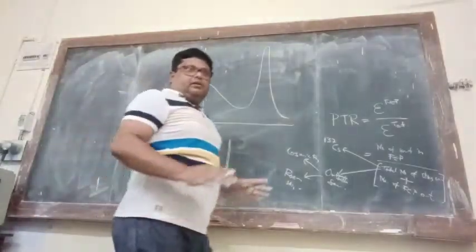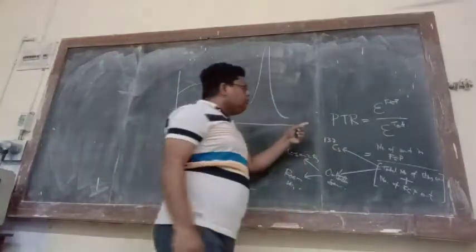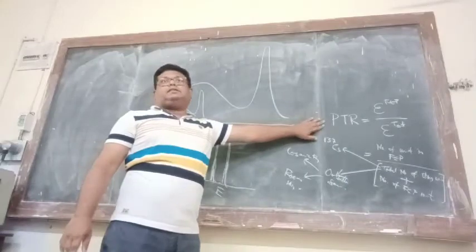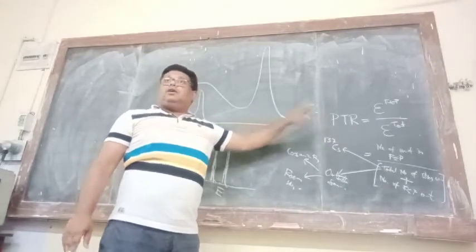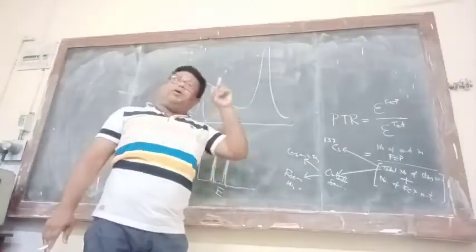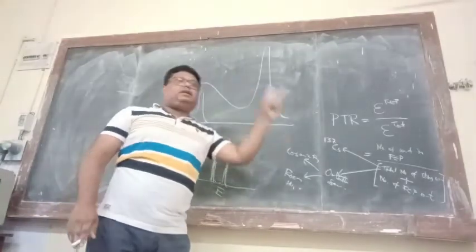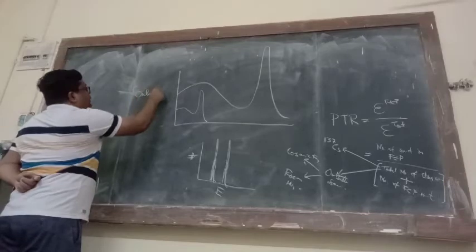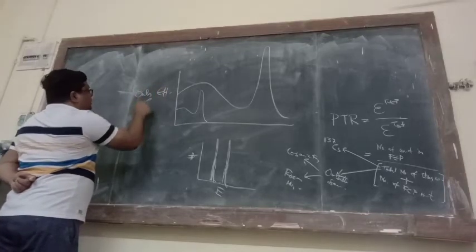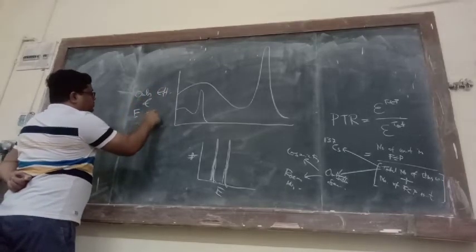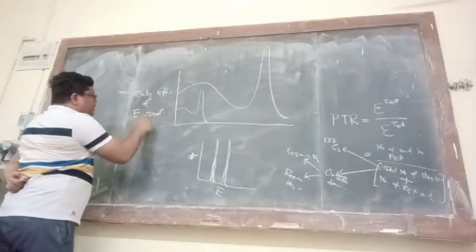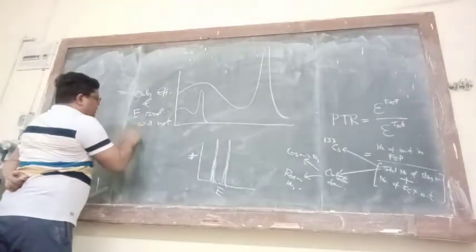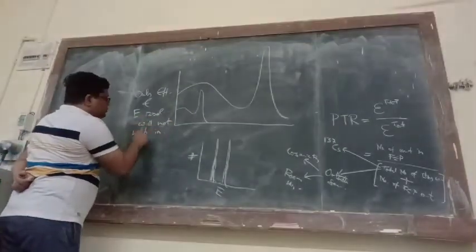So what we need to do here, very important, is maximize this peak to total ratio. Only efficiency and only resolution will not help us. Let me write it down: only efficiency and energy resolution will not help in spectroscopy.